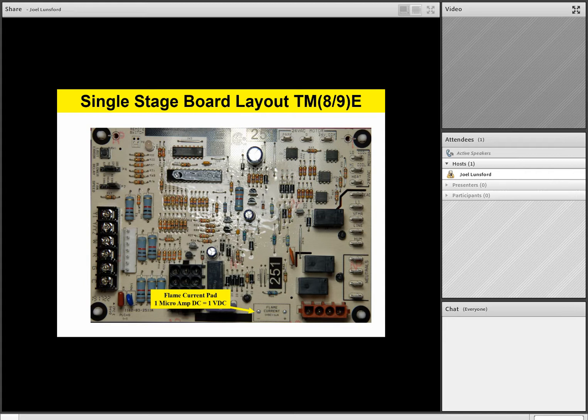And so all he has to do to read flame current is to take his voltmeter and go to DC volts, and as it turns out, 1 volt DC on the flame current pad, right there between those two terminals, you just take your meter leads and put on those little silver terminals. 1 volt DC is equal to 1 microamp DC. Now this is a very important skill that every technician needs, and he should be testing flame current every year.